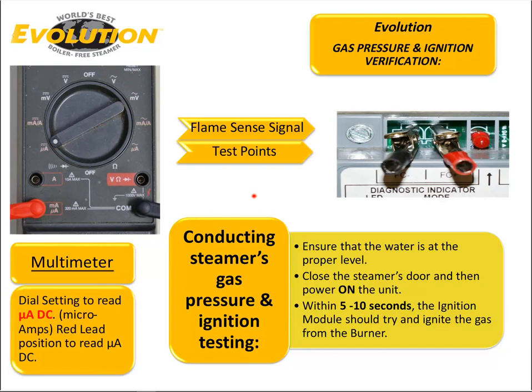You would start ignition. If there is a successful ignition, you should see the flame sense almost immediately. It may start low and climb slightly higher. On steamers, we typically see between 4 and 6 DC microamps. If you see a much lower reading or a much higher reading, this could be a sign that the flame is in the wrong area.